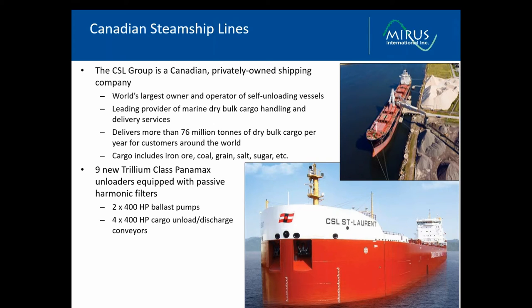Bulk cargo handling ships with self-unloading systems required additional passive harmonic filters after originally failing ABS testing due to high levels of voltage distortion. This was not an electric propulsion vessel. The VFDs were on the ballast pumps and the cargo conveyor system. So you can see there were two 400 horsepower ballast pumps and four 400 horsepower cargo unloading drives for the conveyor system. So quite large drive systems, and harmonic mitigation was applied to that equipment to meet the ABS limits.